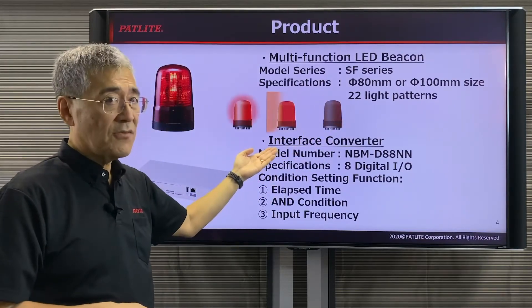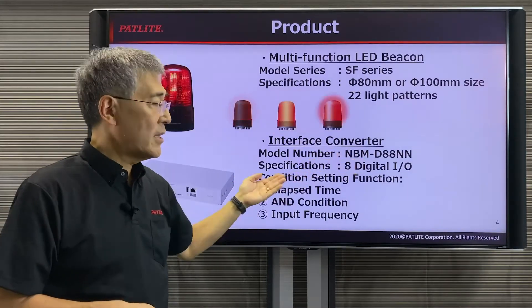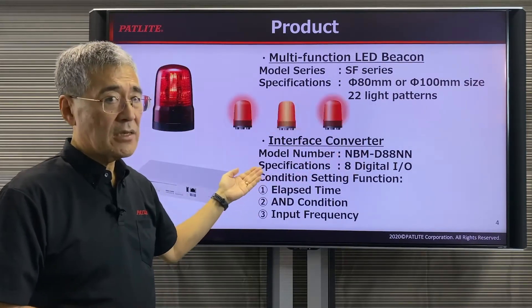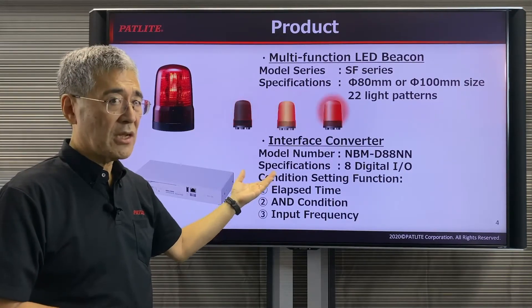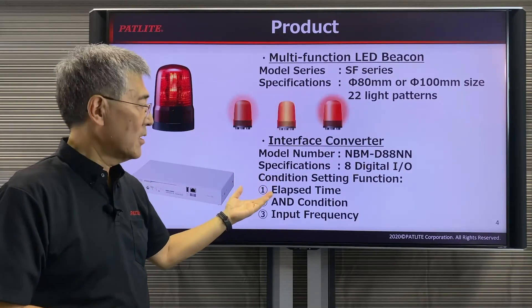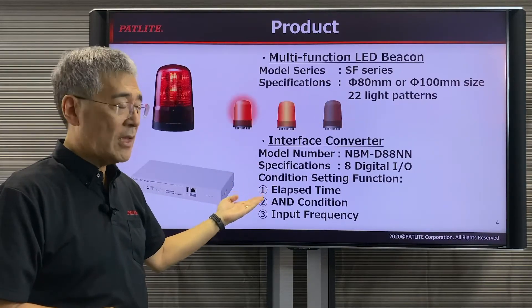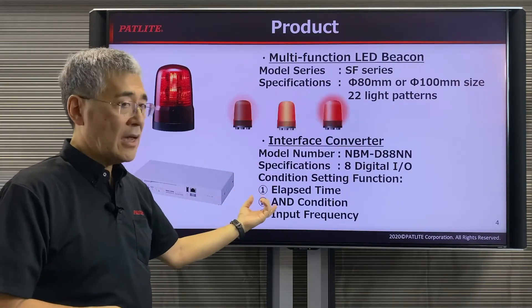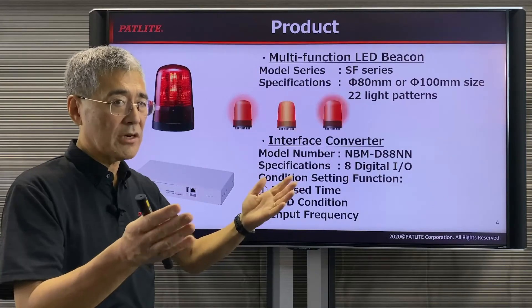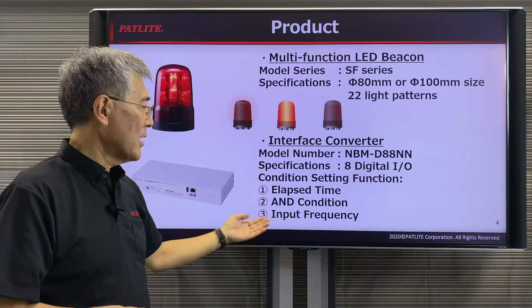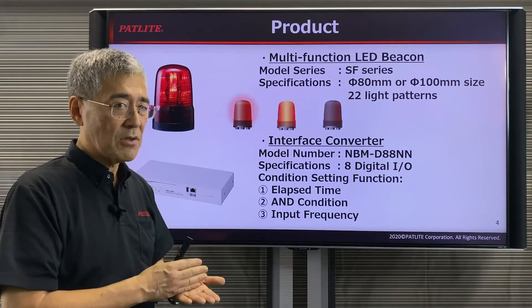The interface converter is the NBM D88NN. It has 8 digital inputs and outputs and has a condition setting function. With this function, you could set triggers based on elapsed time. This AND condition allows you to have multiple inputs before a trigger happens. The input frequency setting depends on how often something happens.